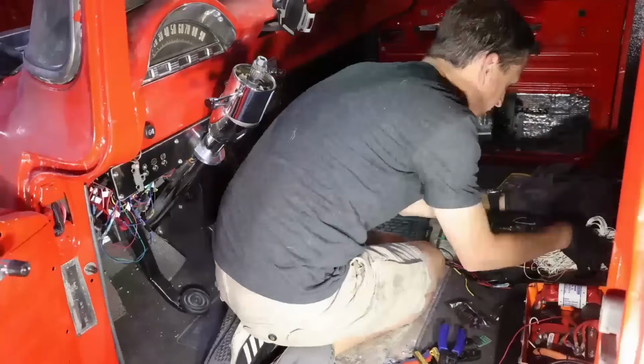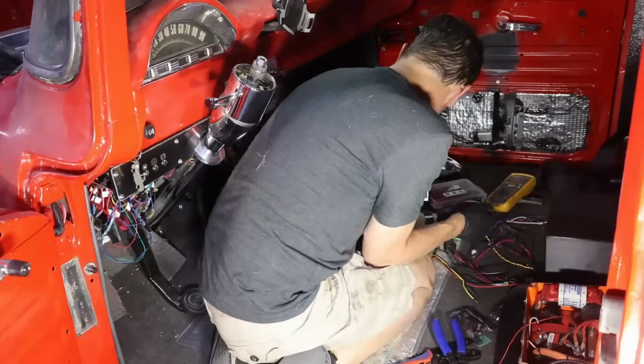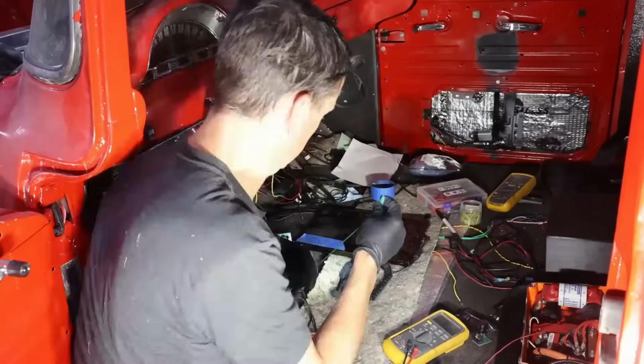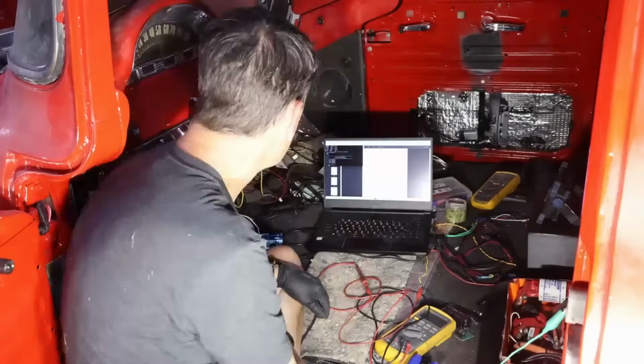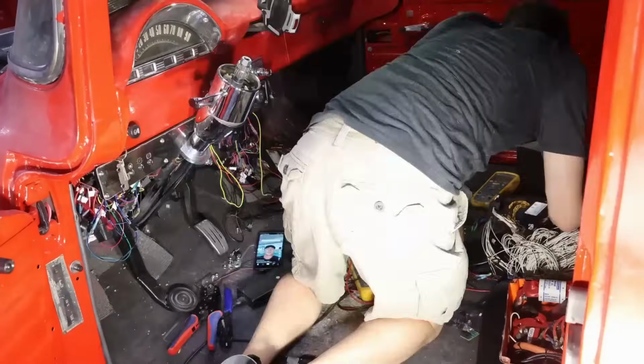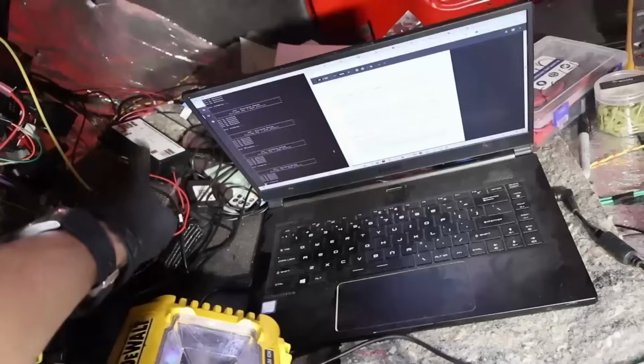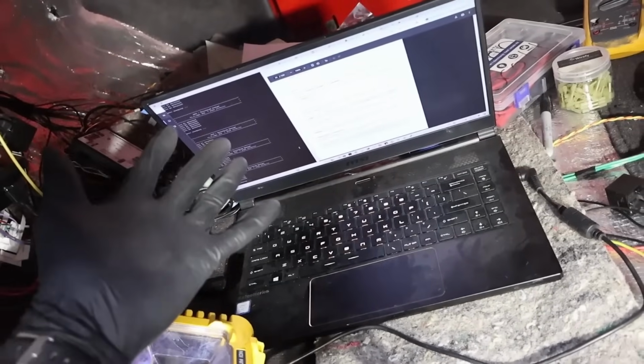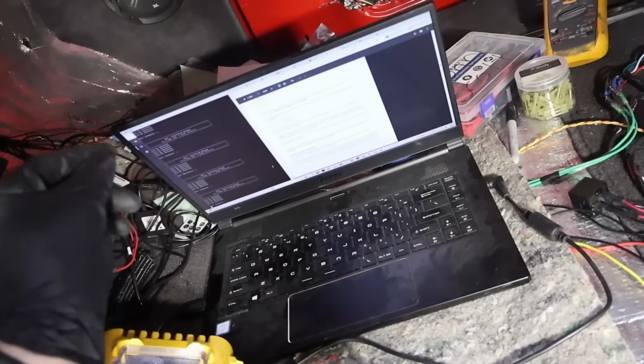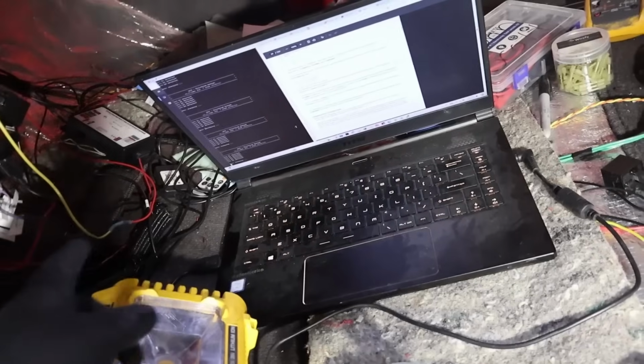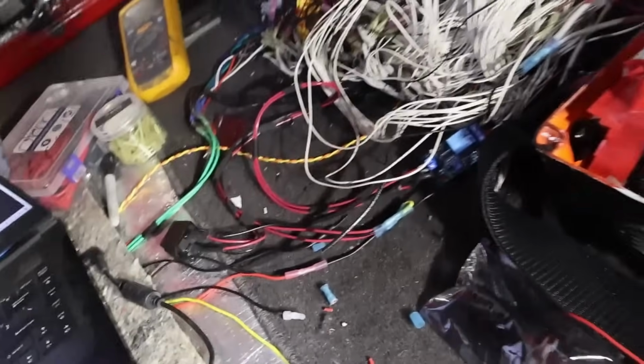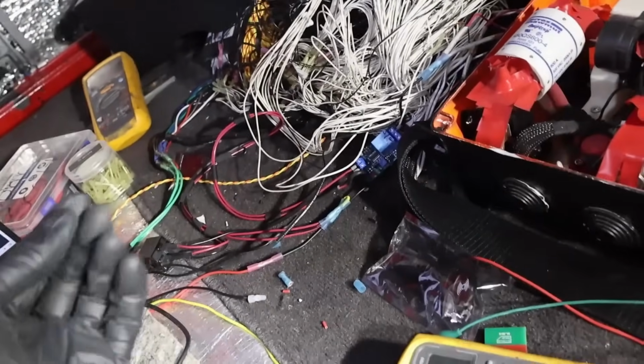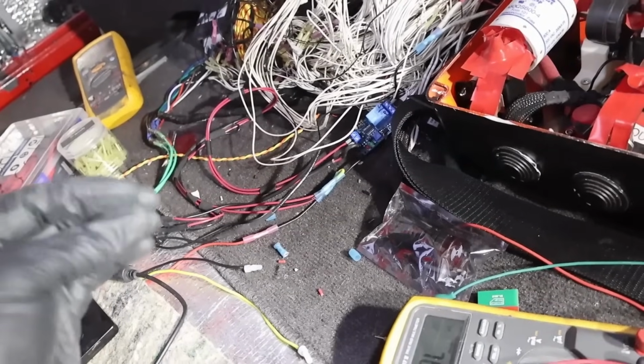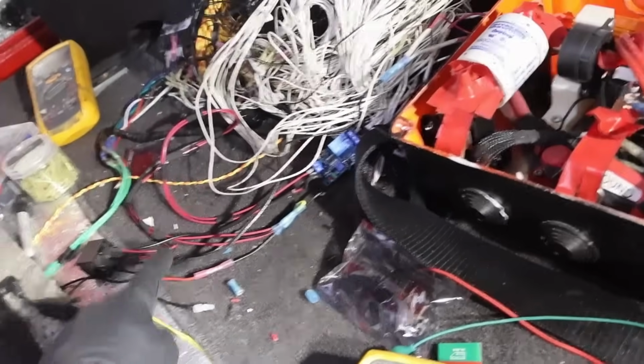I've been rewiring some of the pre-charge circuit. We wanted the pre-charge to come on when we're charging, since the rest of the car is off at that point. The pre-charge was going through the T2C, the motor controller, so we've programmed the BMS so that if there are any faults, it puts out a signal. That signal comes to a relay, set up as normally open, so if it sends the signal, the relay closes.